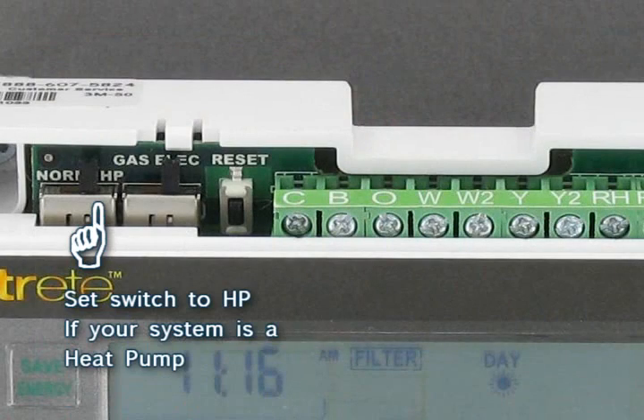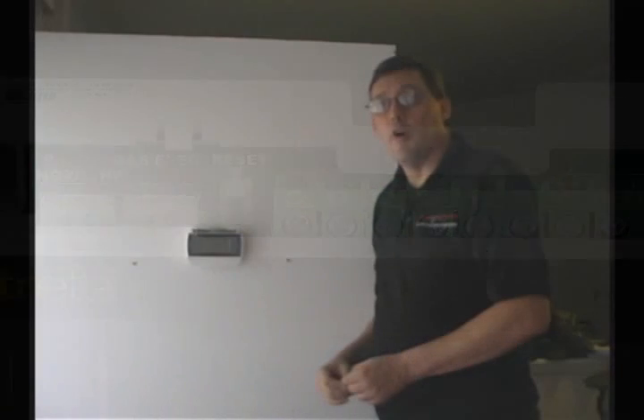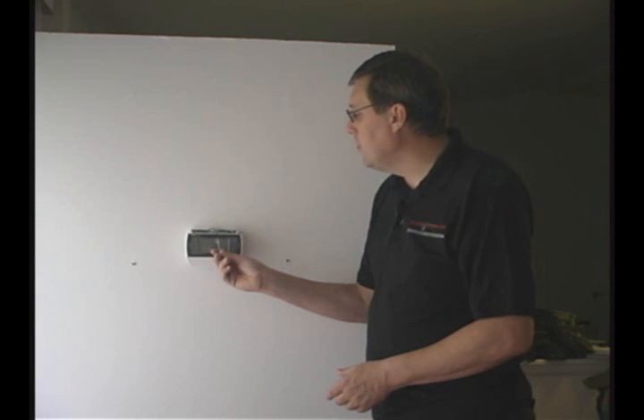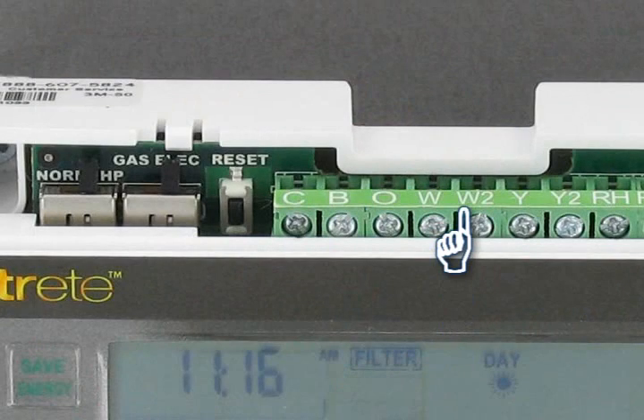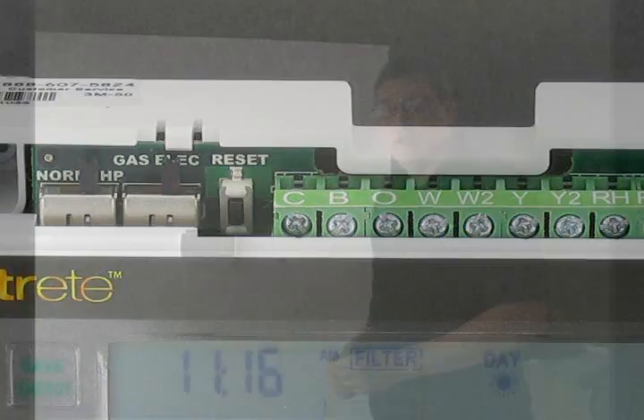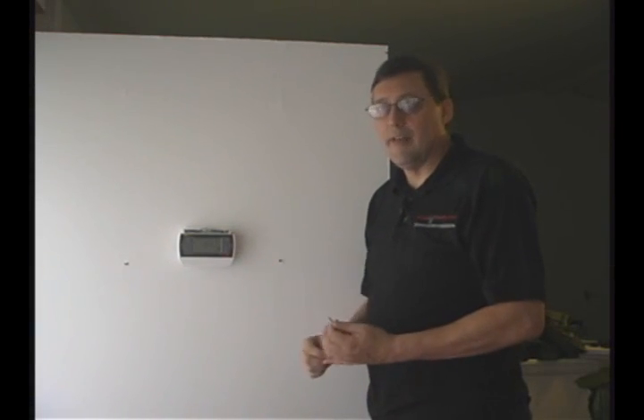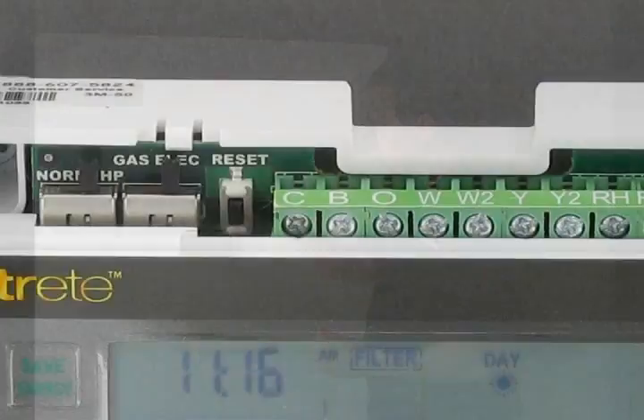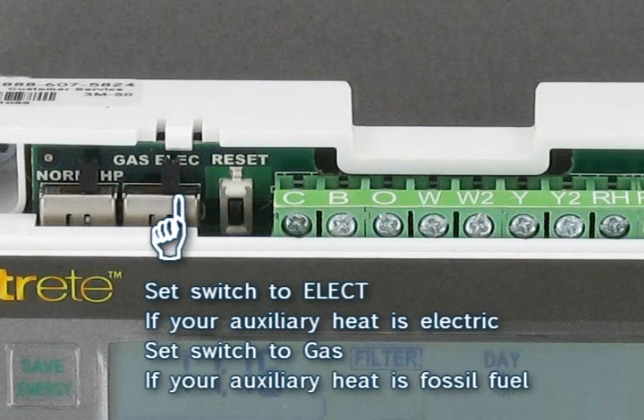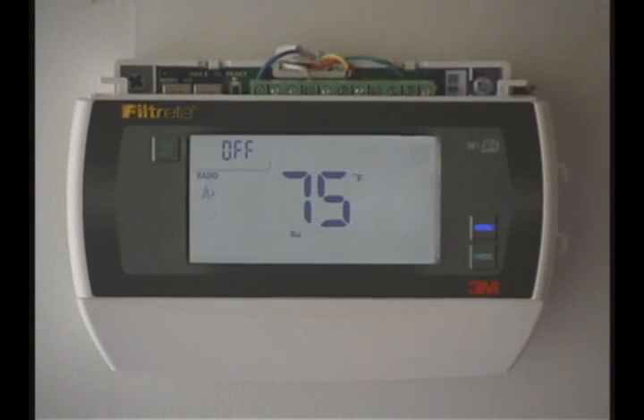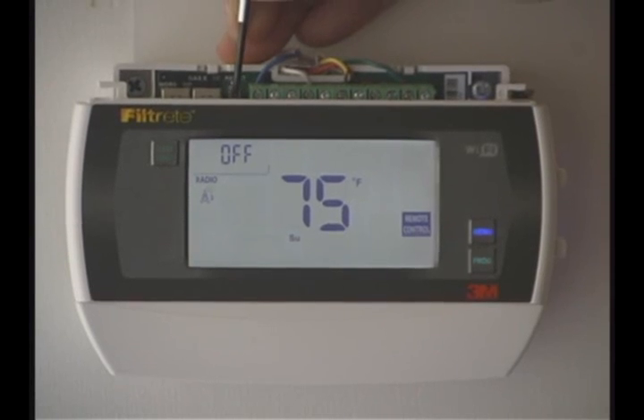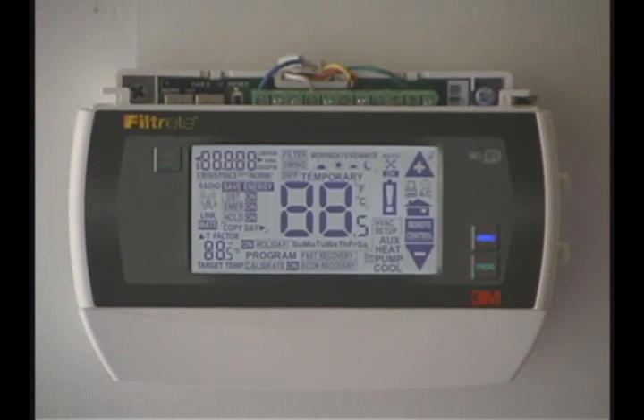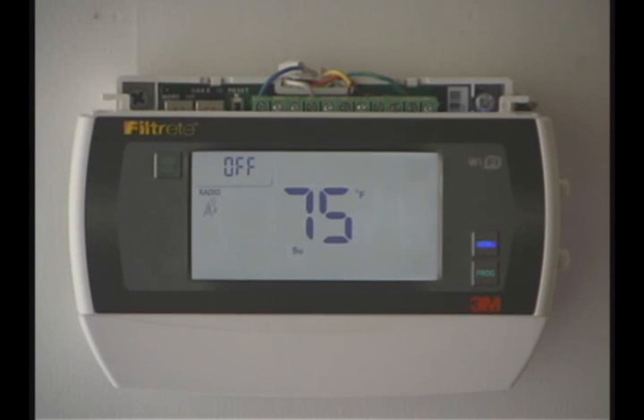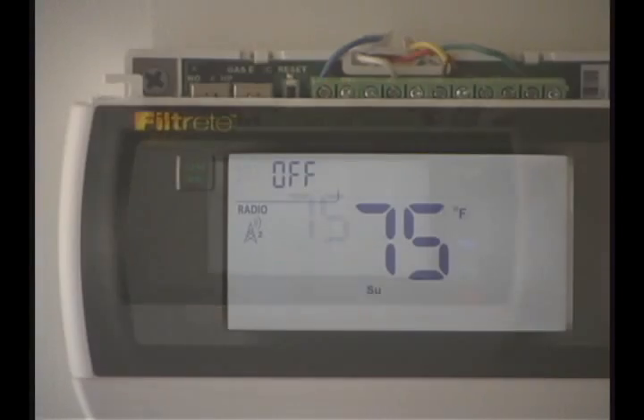So if you switch it over to heat pump, the second button is to say what kind of auxiliary heat you have, if you have auxiliary heat, which would be shown by your W2 terminal here. If you have auxiliary heat, then it's either gas or electric, and we switch this switch for that type of heat. After you do that, we recommend you hit the reset button. Okay, the thermostat will reset, and notice we're still on the off. What we do is we go ahead and we hit the menu button once.